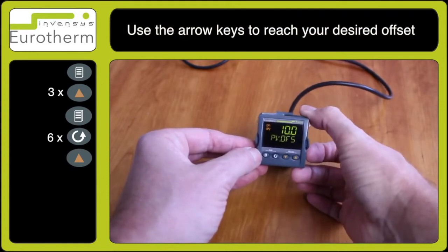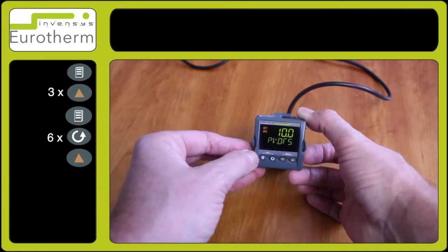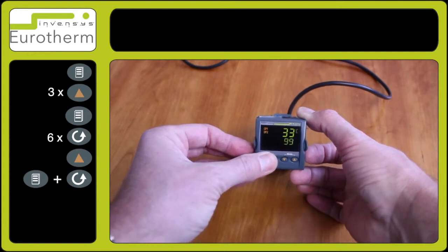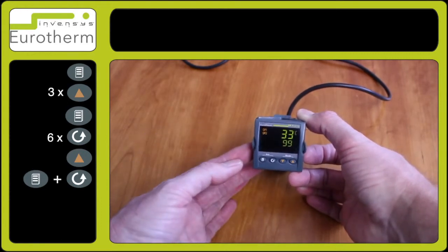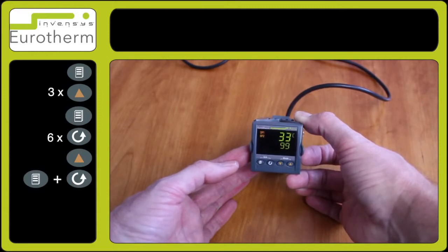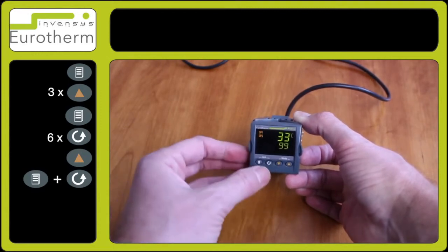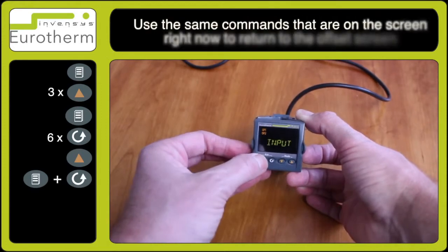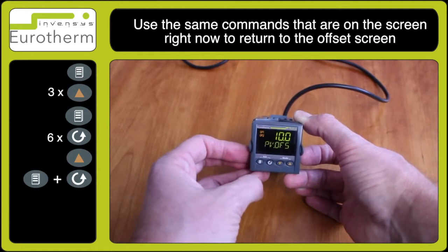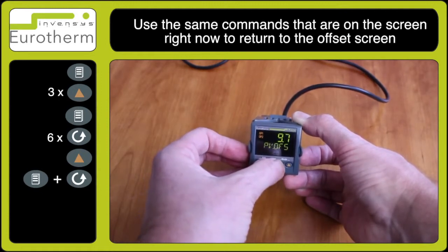place a 10 degree offset on the temperature reading. If I press both keys together, observe 33 degrees on the screen. In actual fact, it's actually 23.